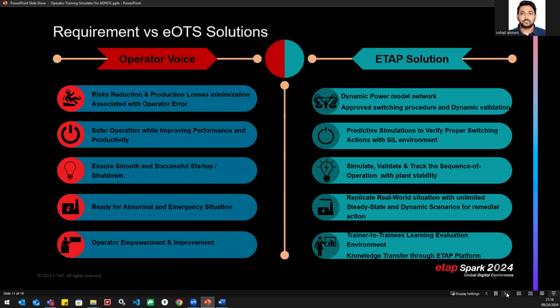One of the major features that is unique to the ETAP OTS solution is system dynamic support. This is because the transient stability engine is utilized within the OTS simulator. This gives the trainees a very realistic window into how the system actually behaves. For instance, when there is a large transformer which is energized, the associated inrush can be seen in the operator screens.